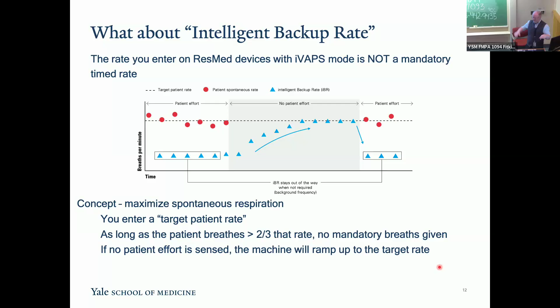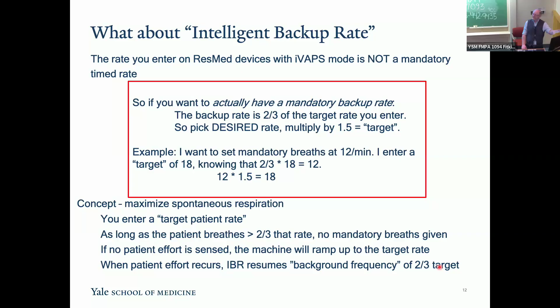And so if you actually want to have a mandatory backup rate, you need to pick a backup rate 2/3 of the target rate that you enter. So if you flip that ratio, pick your goal number, multiply it by 1.5, and that's the number you're going to tell ResMed. So for example, if I want my actual backup rate to be 12, I enter a target of 18 because 2/3 of 18 is 12, i.e. 12 times 1.5 is 18. And that's why that's my preferred prescription on the prior screen.